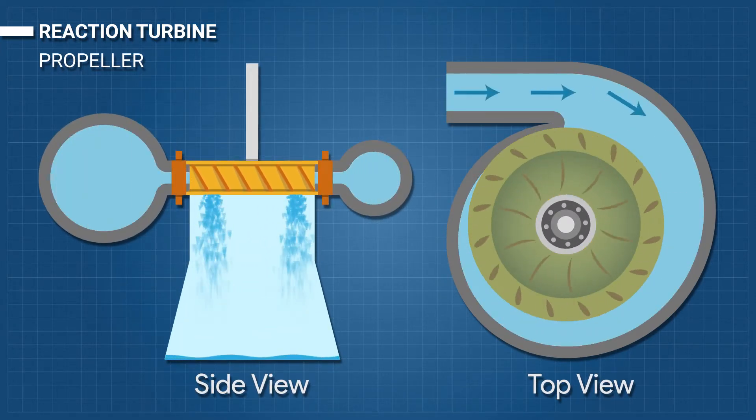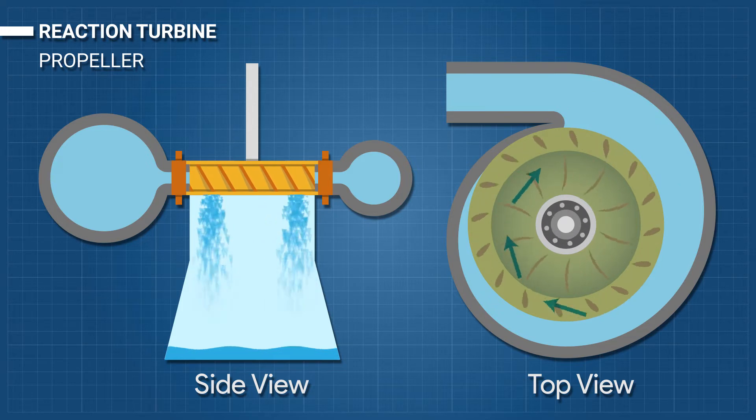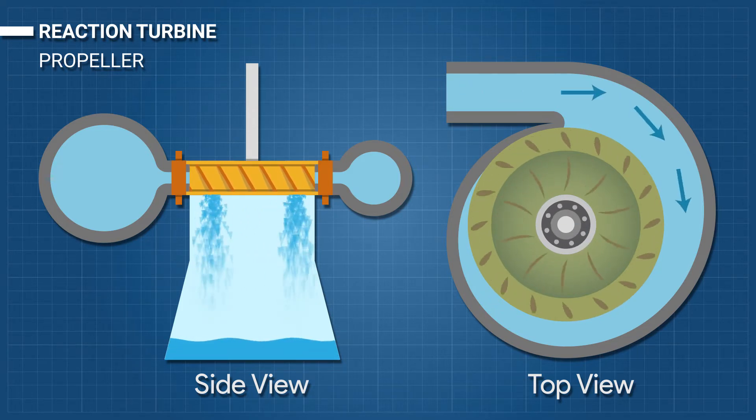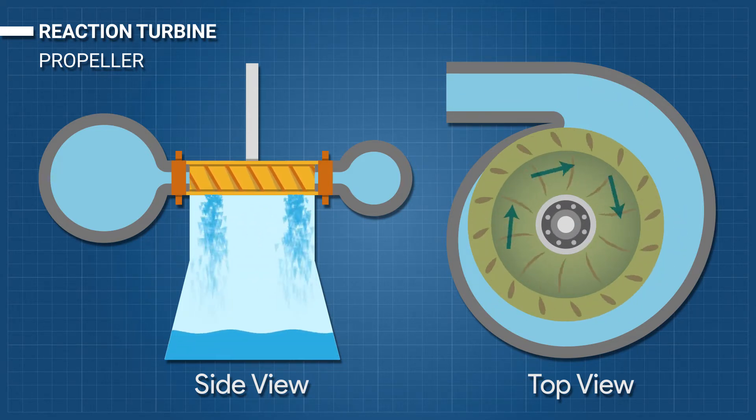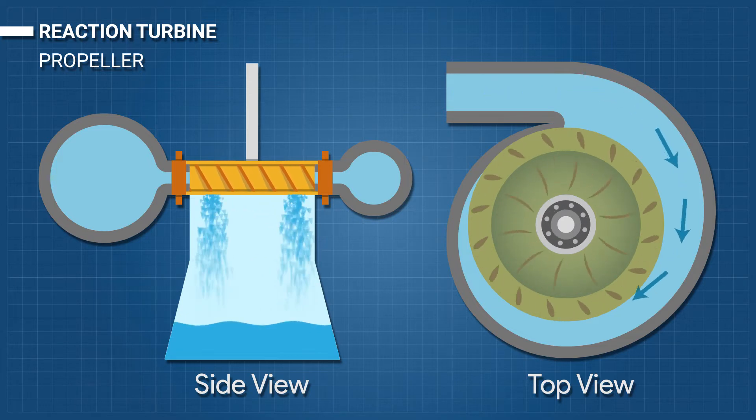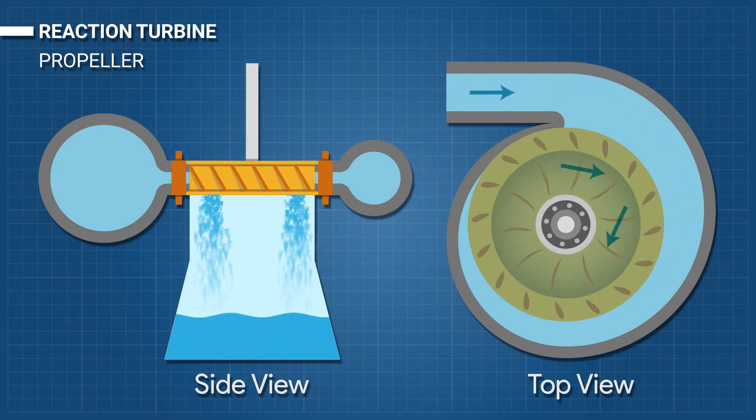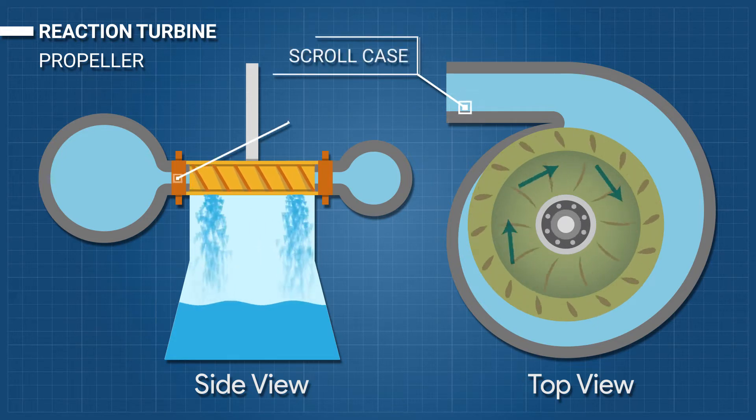Propeller: A propeller turbine generally has a runner with three to six blades in which the water contacts all of the blades constantly. The pitch of the blades may be fixed or adjustable. The major components besides the runner are a scroll case, guide vane, and a draft tube.